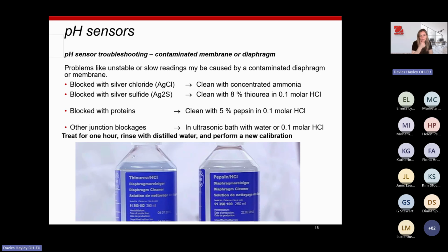If your electrode is blocked with silver chloride, for instance, you can use concentrated ammonia to give that a clean. Give it a wipe with the concentrated ammonia, and then afterwards clean it with distilled water as well. If your probes are blocked with silver sulfide, you can clean with an 8% thiourea in a 0.1 molar HCl solution.